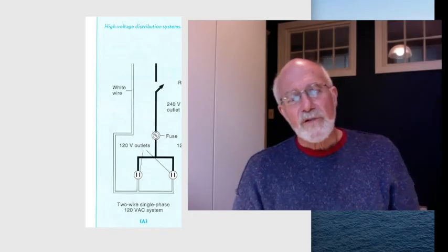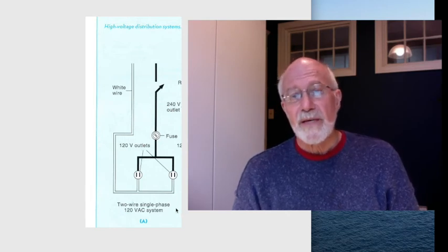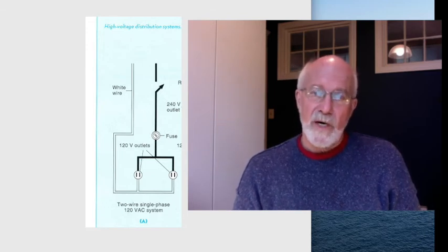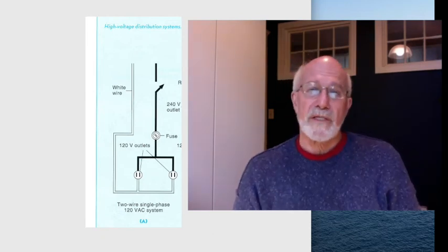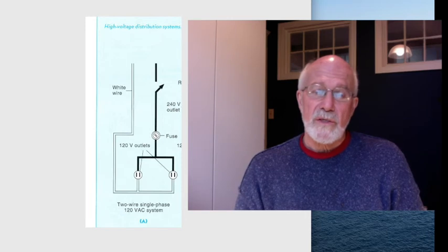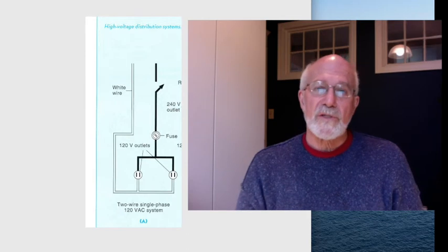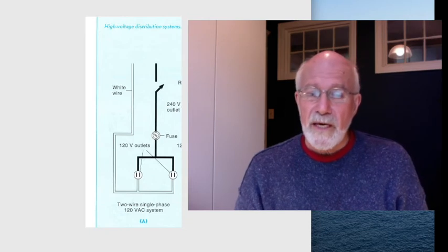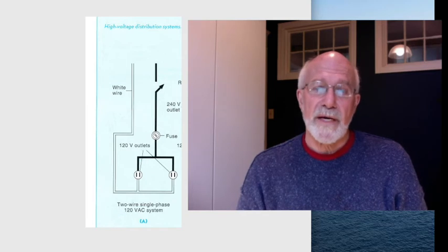What's missing from this drawing, though, is the wiring for the ground, or sometimes it's called earth in Europe. That is another wire that connects anything in the system that you can contact, whether it's the pipes, the outlet boxes, the body of the lighting instrument. If you were able to trace all those connected parts together, you would find out that they literally went to a connection that went right through to earth, right through to the ground.